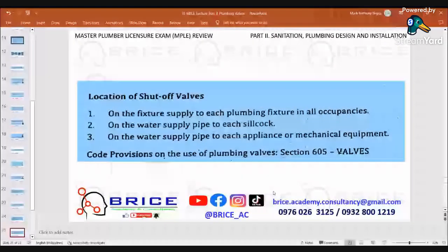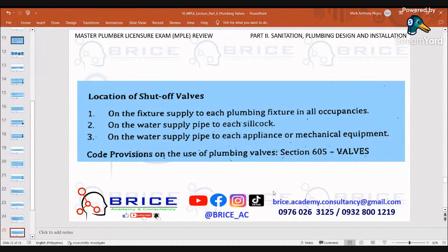Location of shut-off valves. Number 1, on the fixture supply to each plumbing fixture in all occupancies. Number 2, on the water supply pipe to each sillcock. Number 3, on the water supply pipe to each appliance or mechanical equipment. Code provision on the use of plumbing valves: Section 605, the valves.